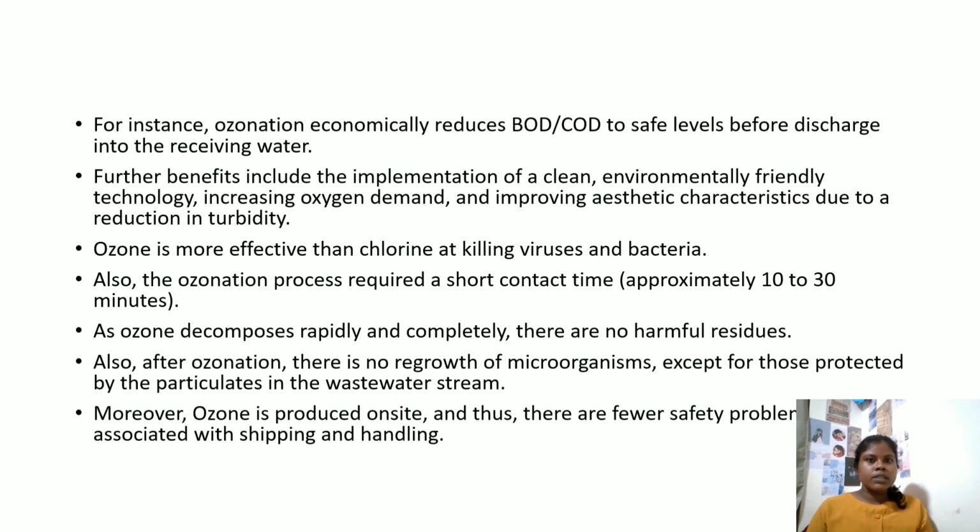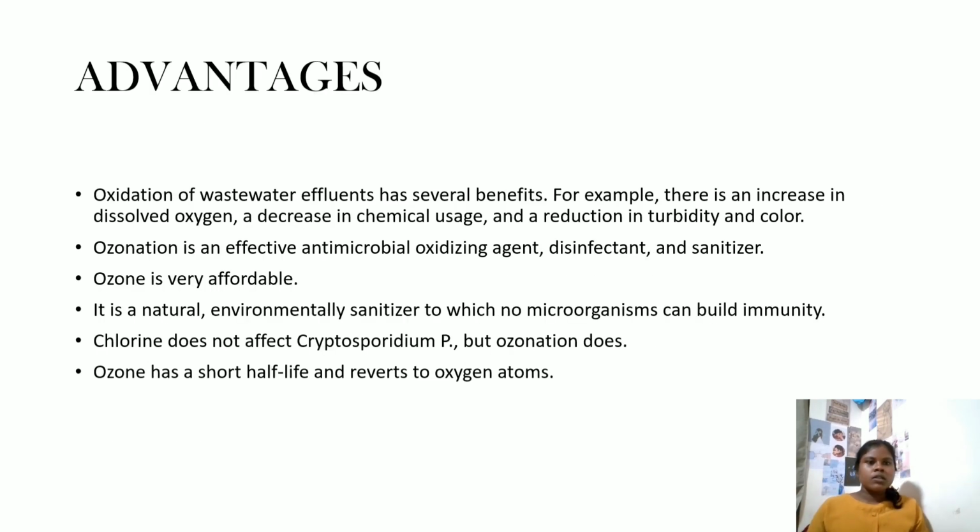In ozonization, it economically reduces the BOD or COD to a safe level before it is discharged into the receiving water, and it is more effective than chlorine at killing viruses and bacteria. It also decomposes rapidly and completely, and there are no harmful residues. Moreover, ozone is produced on site, and thus there are fewer safety problems associated with shipping.